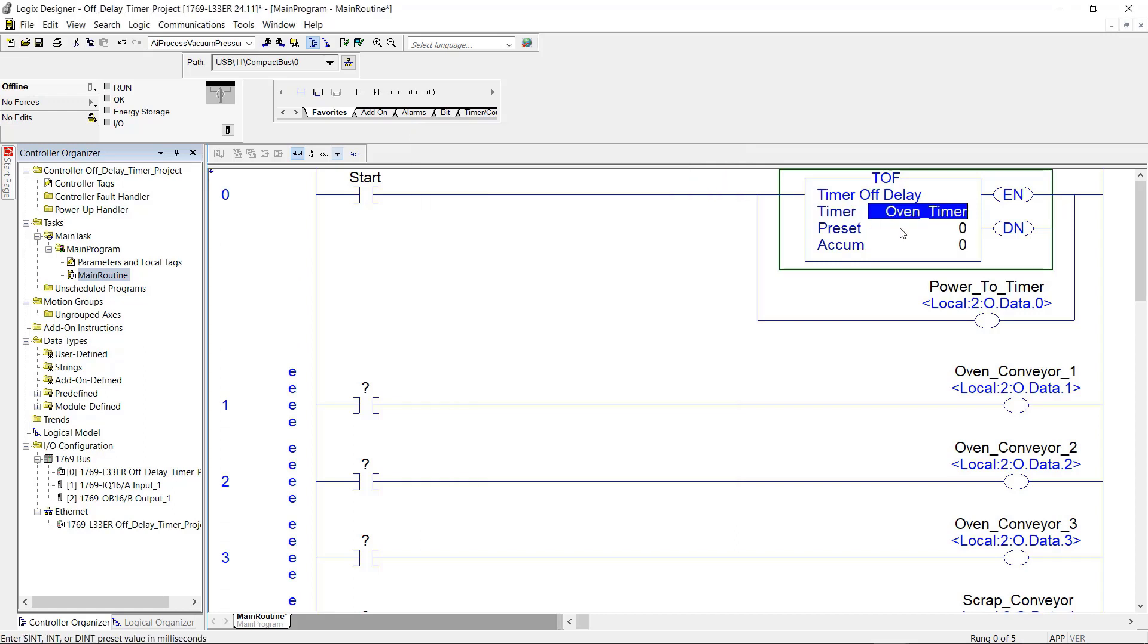Now I'm going to give it a preset. Now you need to remember that this time is in milliseconds. So anytime that you give it time, just add three zeros behind it. One second would be 1,000. Ten seconds is 10,000, and so on.